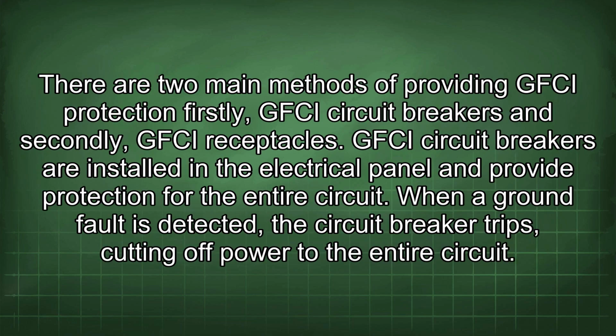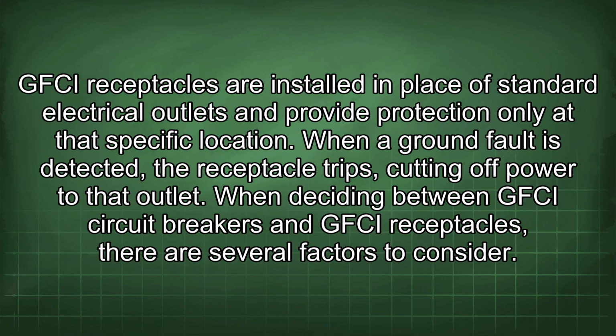There are two main methods of providing GFCI protection. Firstly, GFCI circuit breakers, and secondly, GFCI receptacles. GFCI circuit breakers are installed in the electrical panel and provide protection for the entire circuit. When a ground fault is detected, the circuit breaker trips, cutting off power to the entire circuit. GFCI receptacles are installed in place of standard electrical outlets and provide protection only at that specific location. When a ground fault is detected, the receptacle trips, cutting off power to that outlet.